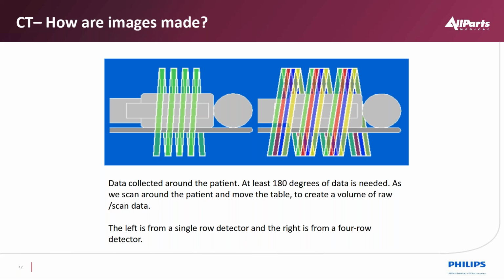Now, as we add 3 more rows, in this case a 4-row detector, as we spiral around the patient, we're building that volumetric data set quicker. But realize from an X-ray energy perspective, we have to have 4 times the energy to be able to have that same amount of dose per slice to create that image quality that we would like. So that's one of the reasons why we have an increase in X-ray tube capacity as far as energy that we have to deal with as well. And then, as you can imagine, we go to 16 and 64 slices and even more. There is a lot more energy that we have to produce more instantaneously for the X-ray tube.